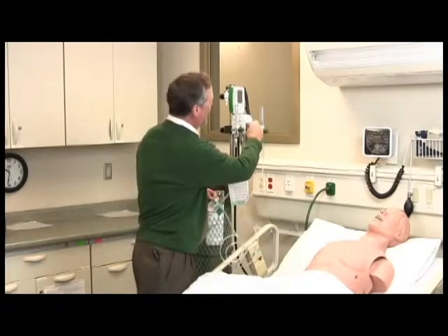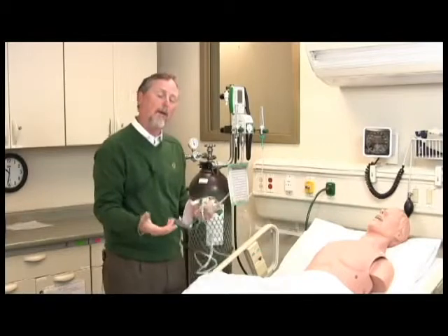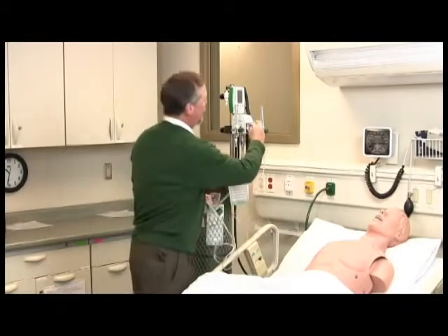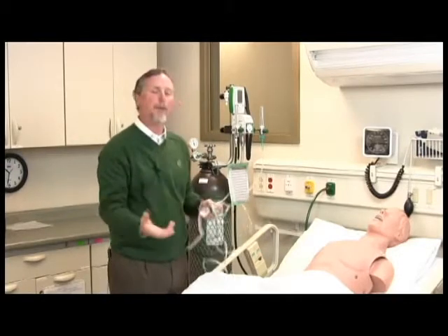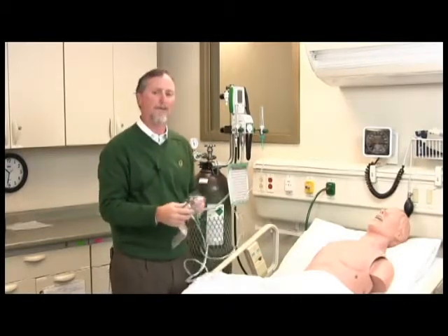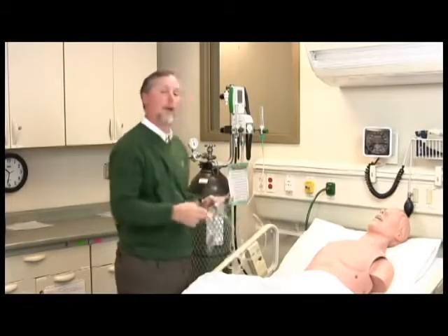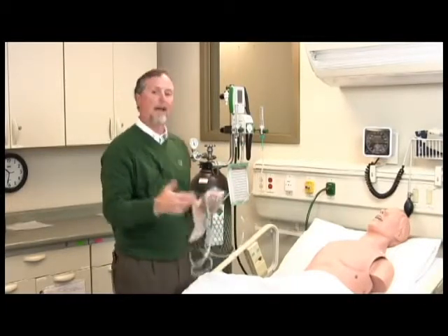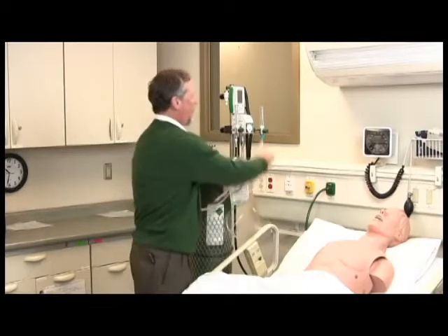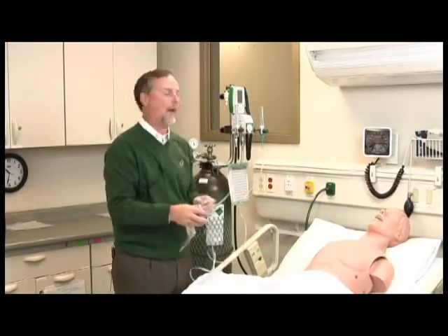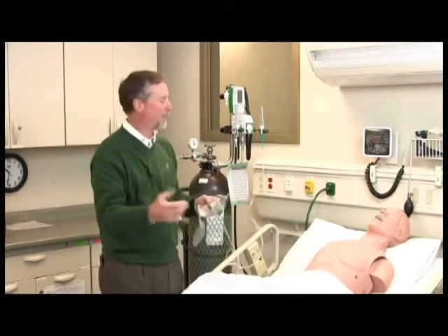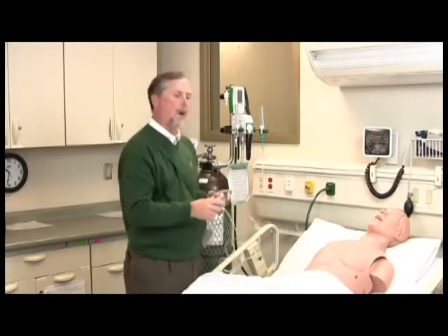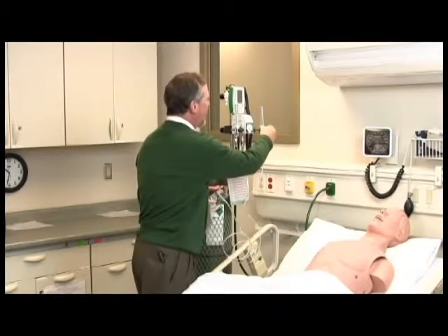Since this is an 80-20 blender, this blender goes from 20% oxygen all the way up to 100% oxygen. And we do 100% oxygen just in case that during therapy, if there's an emergency, the blender can be increased to 100% oxygen. If resuscitation is necessary, you don't have to undo everything and try to go back to the wall outlet. You can just hook up your resuscitation bag to the blender, dial it up to 100% and go from there. So we have this patient that's requiring 40% oxygen, and we'll turn on our flow meter and start flow.